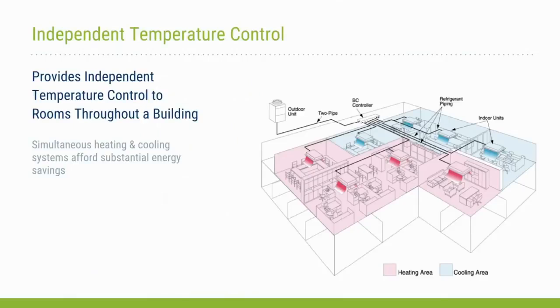This graphic shows an example layout of a VRF system, providing independent temperature control to a variety of spaces. As you can see in the drawing, VRF systems are comprised of multiple indoor fan coil units connected by refrigerant piping to an outdoor unit. The outdoor unit has at least one variable capacity compressor. VRF is an all-electric technology, and there are three primary types of systems. The first type is the air conditioner, and this type of VRF system only provides cooling. The second type is the heat pump system. This type provides both cooling and heating, but it can only provide heat transfer in one direction at a time. So in other words, the whole system operates either in the cooling mode or in the heating mode.